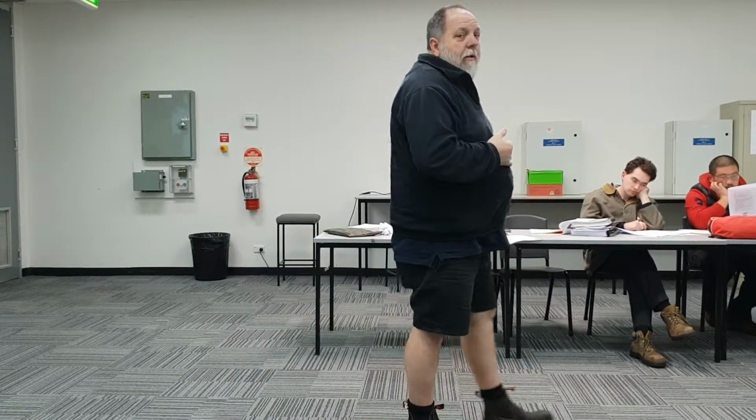What does the power point say in the third or fourth column there? 10 amps plus 5 amps per living unit. So if I had 6 units, it'd be 5 times 6, plus the 10 on the end. Does that make sense? So you work your way through it.